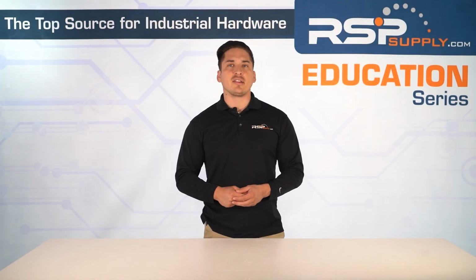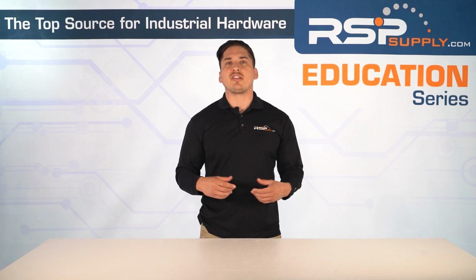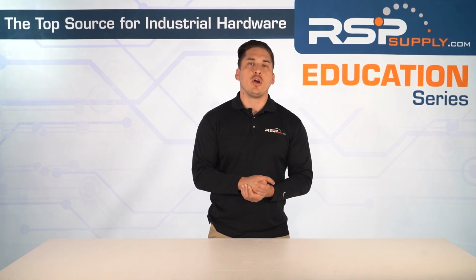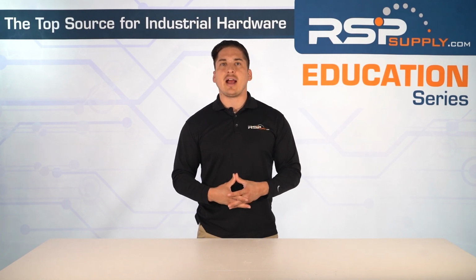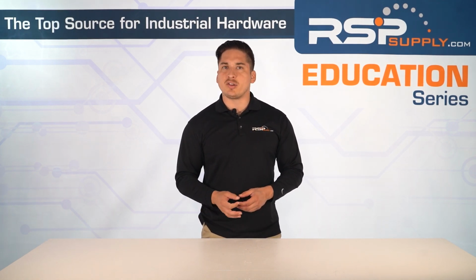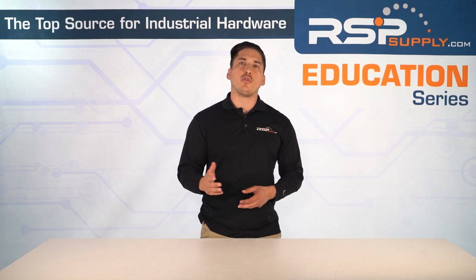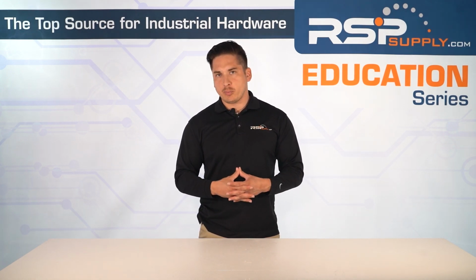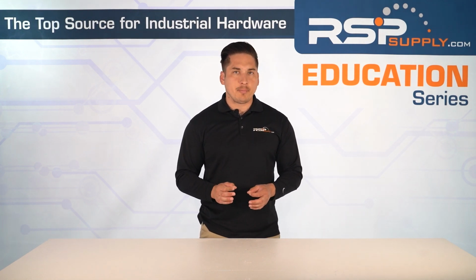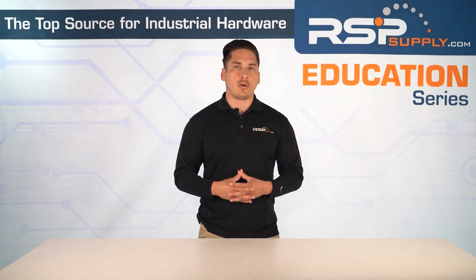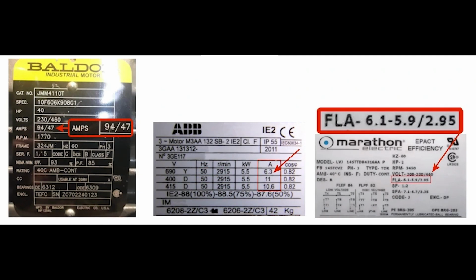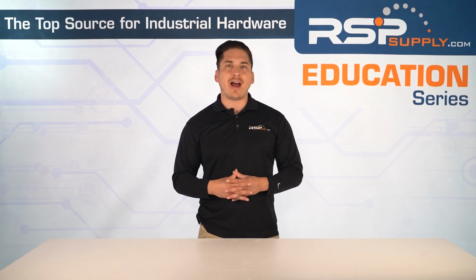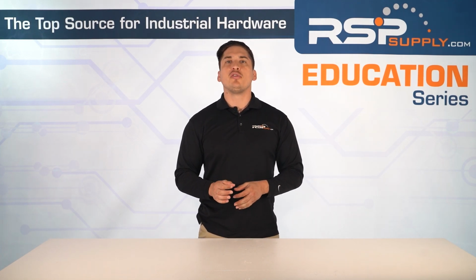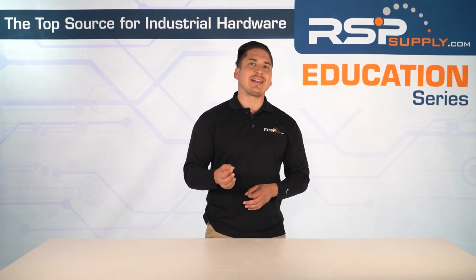So when you're sizing and selecting a disconnect switch, you need to consider voltage and current ratings primarily. Make sure the voltage matches your system, whether it's AC or DC. When you're choosing a disconnect, it's key that its voltage rating meets or beats your system's voltage. Whether that's 120 volt or 240 volt or 480 volt, make sure it's a match. And remember, AC and DC ratings aren't the same. A switch rated for one doesn't automatically work for the other. A current rating should cover the load amps plus a little more. Check the full load amps, or the FLA, of your system and pick a disconnect that's rated a bit higher. Most people give it about 10 to 25% cushion. If you're working with motors, use the FLA from the nameplate or NEC chart to guide your choice.